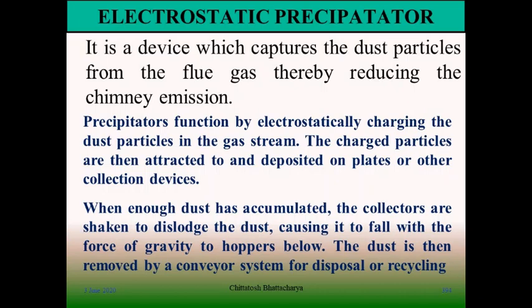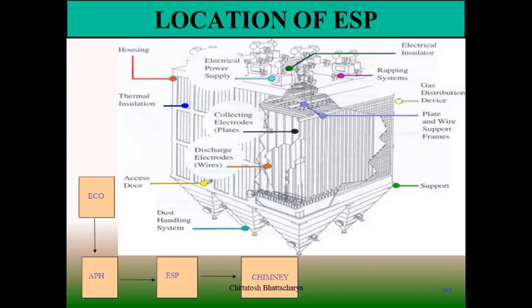When enough dust has accumulated, the collectors are shaken or rapped to dislodge the dust, causing it to fall by gravity into a hopper, from where it is evacuated and passed through a conveyor system to dump it. The clean flue gas exits through the chimney. The ESP inlet is provided with a gas distribution device so that the velocity of the inlet can be distributed uniformly. There are discharge electrode wires, emitting electrode wires, and collecting electrode plates placed in parallel.